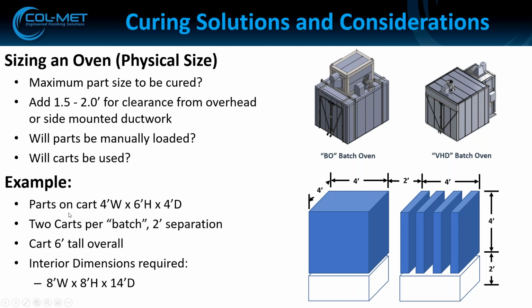Once that's understood, let's look at an example: a cart that's 4 foot wide, 6 foot high, and 4 foot deep. The customer wants to put 2 carts in the oven at a time with a 2 foot separation, allowing someone to get in there and back out and also have good airflow around the parts. Adding 2 feet around each side: for width, 4 feet plus 2 on each side gives 8 foot wide. For height, the cart is already spaced 2 feet up with the part suspended, so 6 foot plus 2 gives 8 foot high. And for depth, 8 feet of carts plus 2 feet between them plus 2 feet on each end gives a 14 foot depth. So that's the size oven we're looking for.